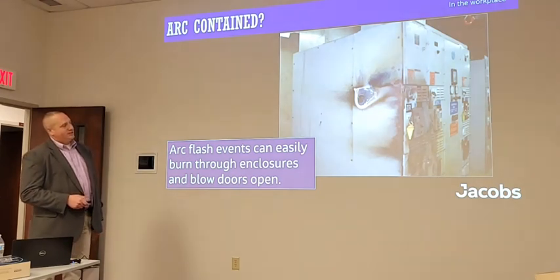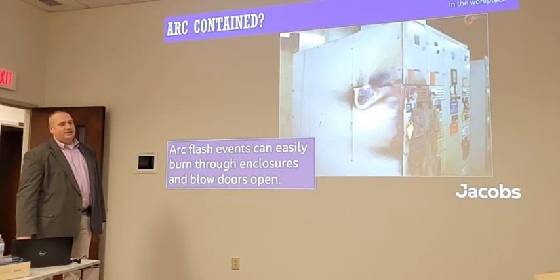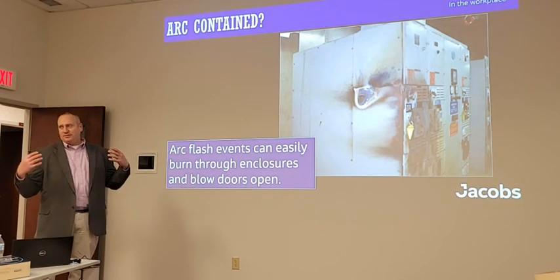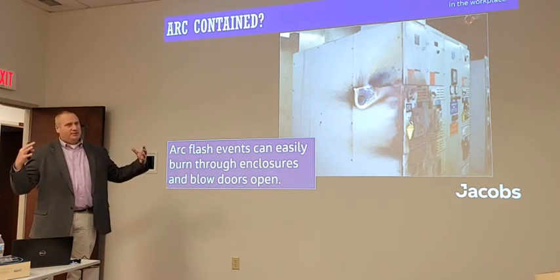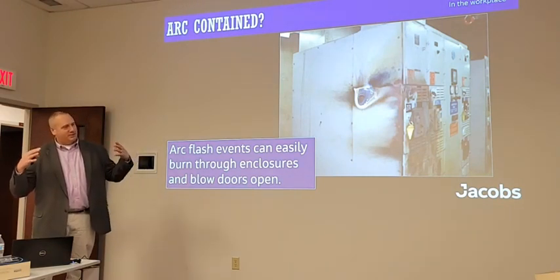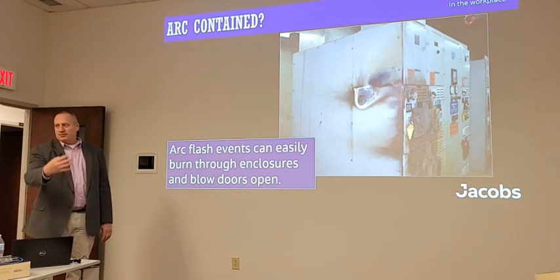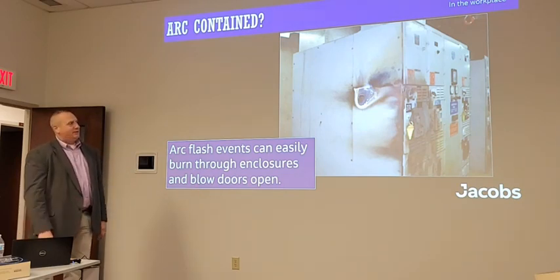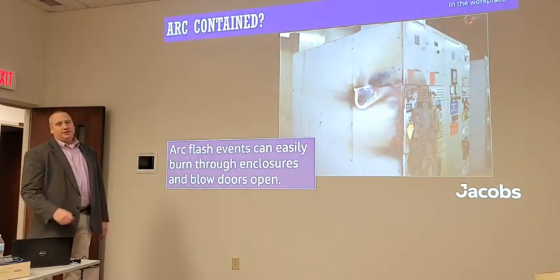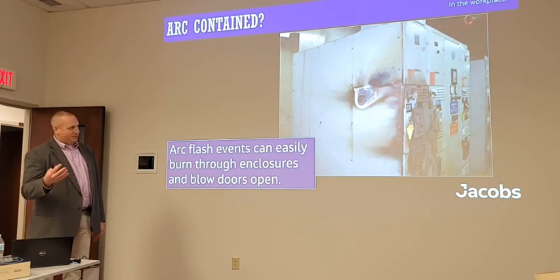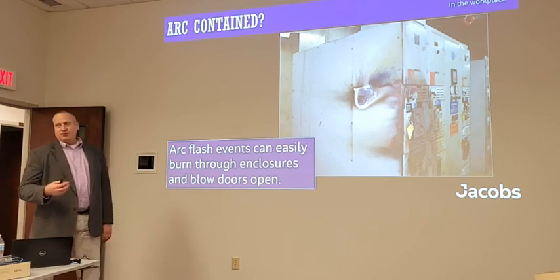But the reality is, you can look on the front here, and most of your electrical gear, unless it's arc rated, is going to have some ventilation. And so at the very least, you're going to have all that rapid expansion wants to escape somewhere. Where is it coming out? It's coming out the vents, which are typically right in the front, right where somebody would be standing. And if the vents aren't enough to vent it out, then it's going to rip the bolts off, rip the latches off, and blow the doors open.